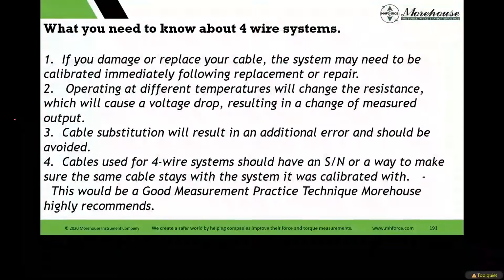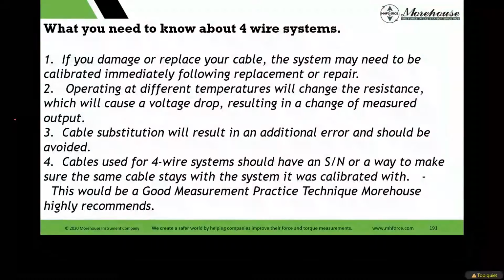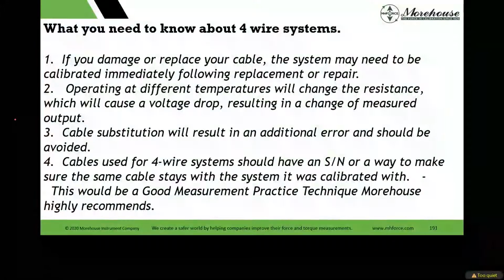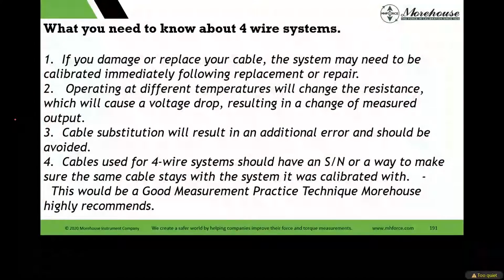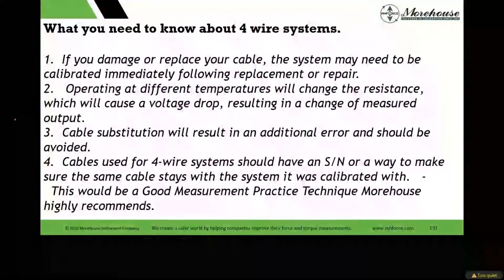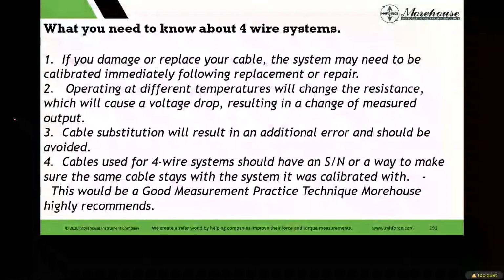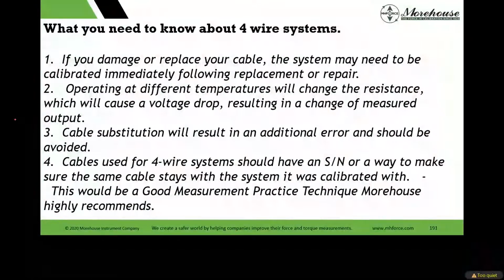If you change cables on that, which we have one customer that does, they send us a 20-foot cable one year and a 10-foot cable the next year, and then their change from previous never meets the stability requirements for ASTM because of the change. It's problematic. So the recommendation, if you're using a 4-wire system, is basically that you put serial numbers on the cable, and you make note that you only want to use that one cable.